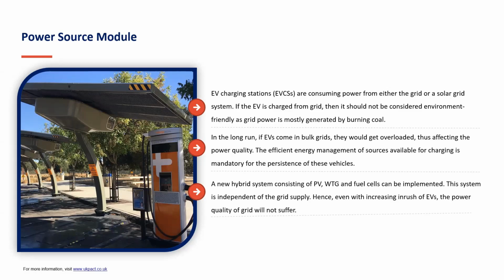Since we talk of DC charging right from say 25 kilowatts onwards to hundreds of kilowatts, nowadays you also get 300 kilowatts, 400 kilowatts. You would definitely need to plan the grid capacity accordingly. If you have a charging station with many chargers, and the grid connectivity is not sufficiently planned, it would mean trouble for the grid operator. That's why when you set up a charging station, consultancy should be done as to what is the available grid power and what is the expected power which will be taken up by these chargers, and thereby the grid capacity should be planned by installing new transformers or connecting to HT lines, etc.